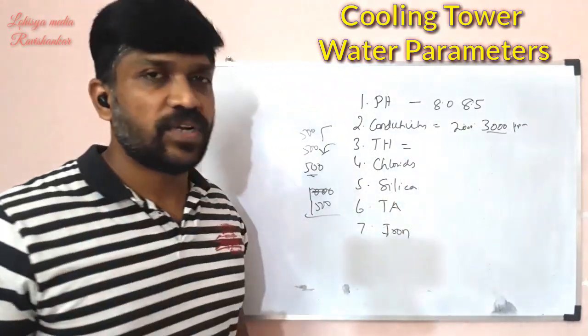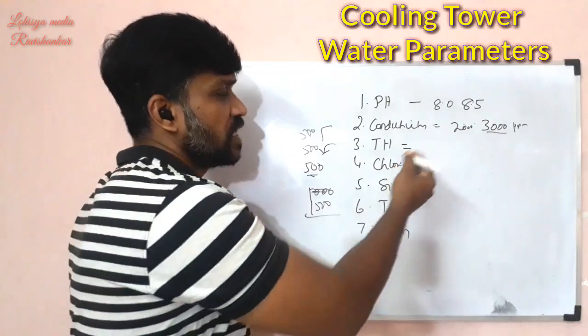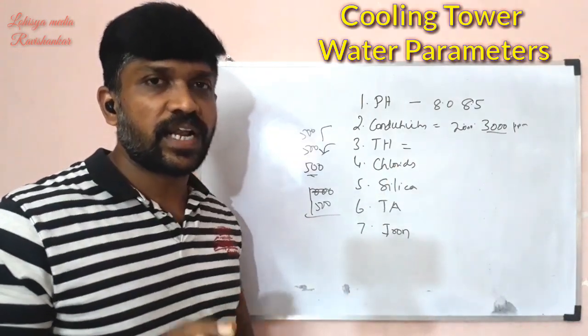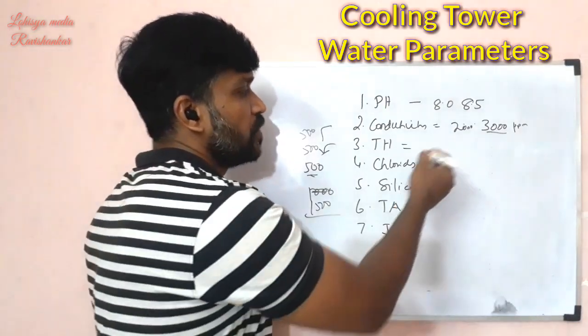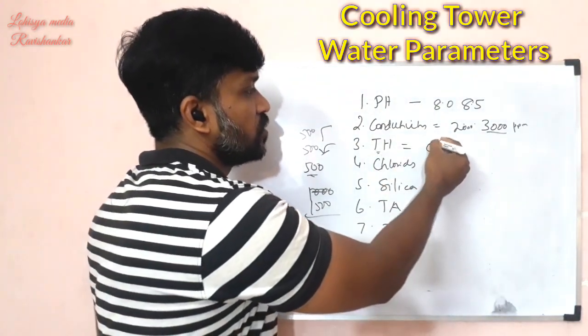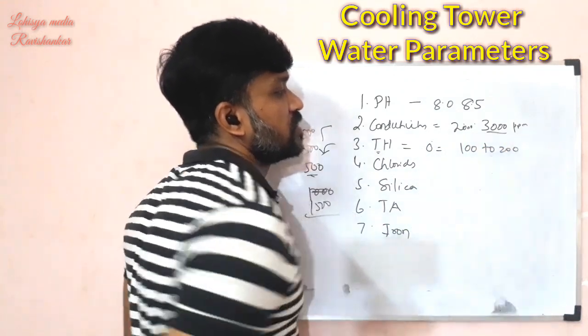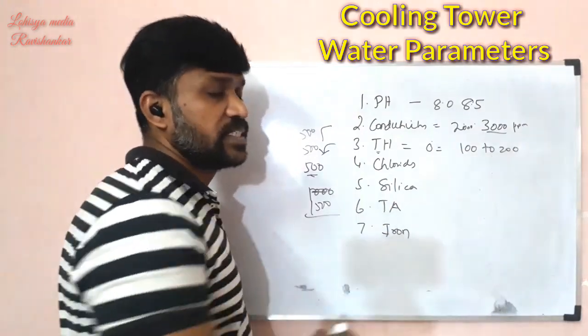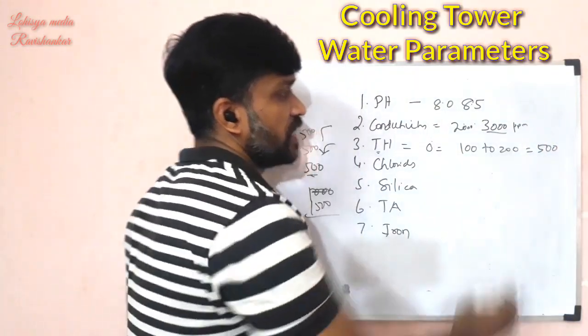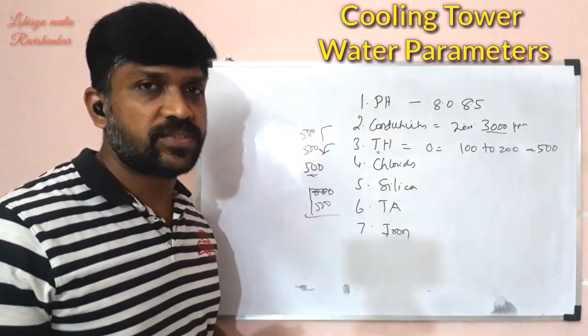For total hardness, if you use soft water, the hardness will be near zero, but we can maintain 100 to 200 PPM. If you use harder water, total hardness can go above 500 PPM, so we need to monitor this carefully.